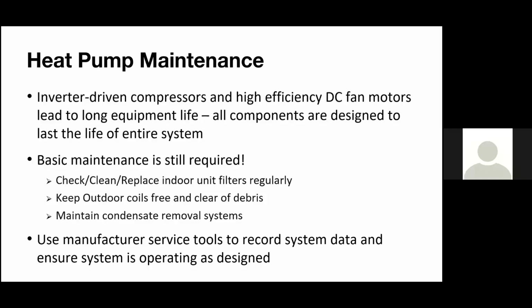So basically that filter wasn't cleaned for 4 or 5 years, which, for a small DC fan motor in a wall mounted unit, it was ductless, didn't have the external static pressure to actually push that air through that dirty filter. So something to take away from that story is, when you're doing regular preventive maintenance, check your filters every 6 to 8 months just to see if they're clean and good to go, so we don't reduce any operation that's set to do.